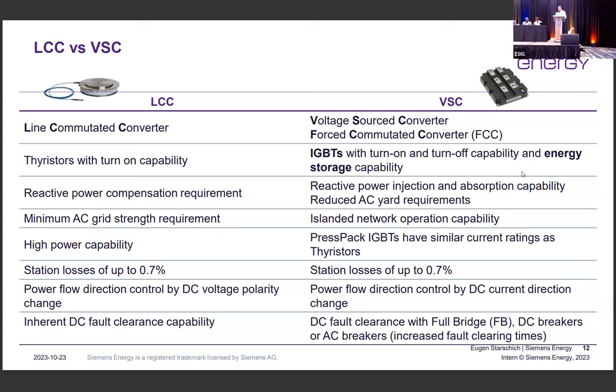Yeah, but this is an intention. It is not a real project. It's the plan. That is the problem. It's the plan that says, okay, you want to have a DC breaker. What is your specification? What is the fault clearing time? As long as there is no specification on the fault clearing, it's very difficult to sign up and say which technology to go with. Hybrid might be sufficient. Okay, then all the vendors will build the hybrid DC breakers. But if we say no, we need a fault clearance time of less than 1 millisecond, we will need to go with the solid state breakers.